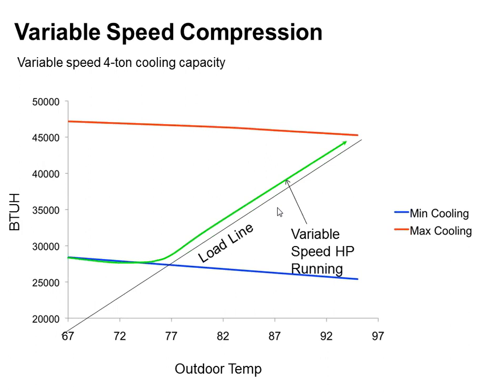The third time that it's going to cycle off is if it's so mild outside it can't ramp down far enough. It'll have to actually shut off. That's only going to happen between probably 50 and 75 degree outdoor temperatures. Anything colder than that or hotter than that, it's going to be running.